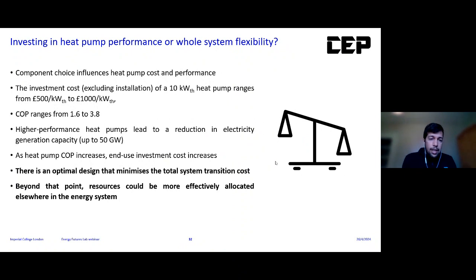So that's the grasp of what we did, and I'd like to conclude with this consideration: is it worth investing in heat pump performance, or in whole energy system flexibility? In this work, we've shown that component choices significantly influence heat pump cost and performance, with investment cost varying between about 500 and 1,000 pounds per kilowatt for air to water heat pumps, excluding installation costs. The COP can also more than double if you switch from low to high performance.